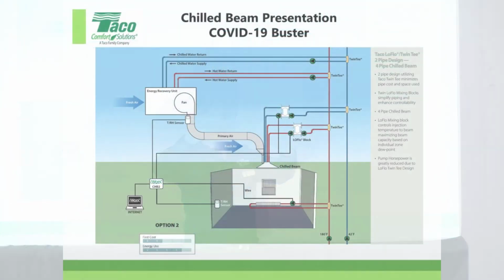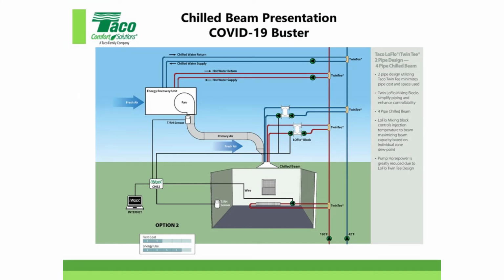So in my normal piping systems, I still have two lines there, right? Yep, and same thing on chill, but there is a cascade of temperatures. So in that case, it would be 160, call it. I'm going to make up some numbers, right? So maybe I have 100 GPM in here, I only pull off 5 GPM for this. So it's going back in at 160 into here. So instead of reducing it to 160, it only reduces it down to 178, maybe, because you're mixing it. And then we've got to control the flow rate to make sure the cascade doesn't go crazy on us. Great point, for sure.